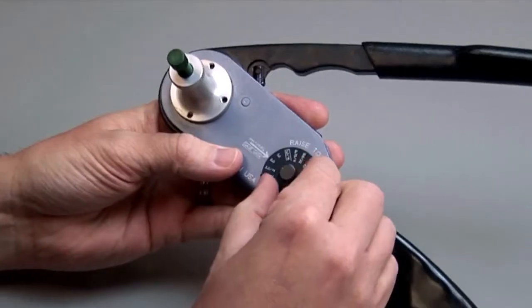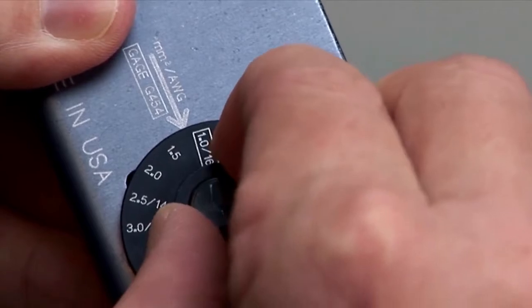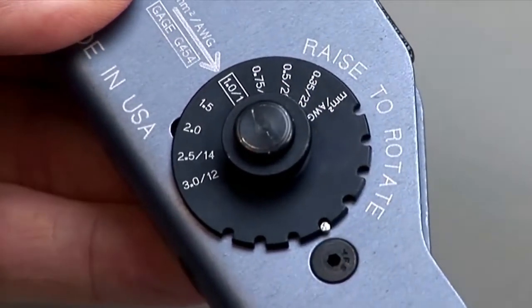Begin with a stripped wire. On the crimp tool, raise the selector knob and rotate it until the arrow is aligned with the wire gauge to be crimped.